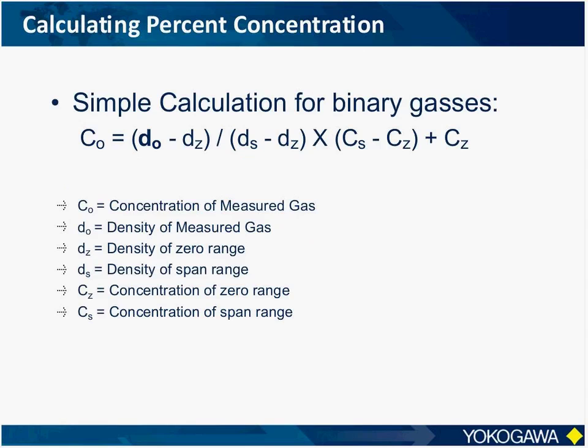Now, by measuring density in a binary gas stream, we can calculate percent concentration based on a simple calculation. So we have known values for the constants, and these are the zero and span concentrations and their associated densities. The only variable is the actual density of the gas, which is dependent on the concentrations of the two gases in the process stream.